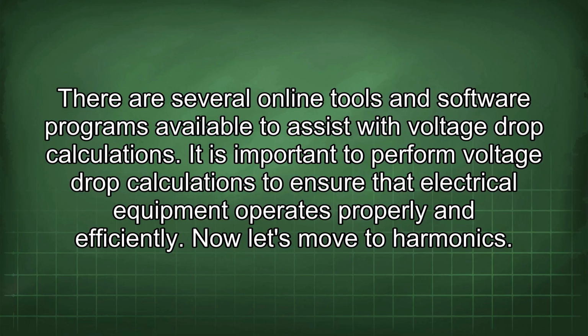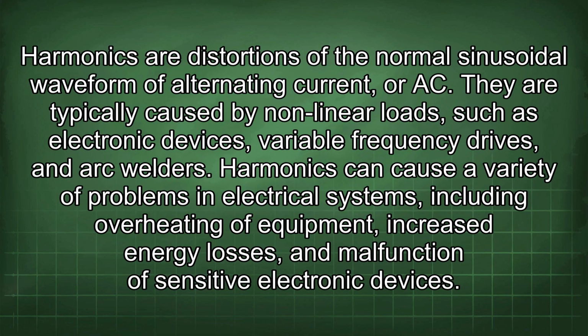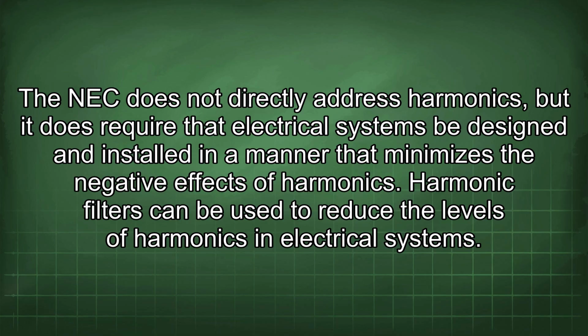Now let's move to harmonics. Harmonics are distortions of the normal sinusoidal waveform of alternating current, or AC. They are typically caused by nonlinear loads such as electronic devices, variable frequency drives, and arc welders. Harmonics can cause a variety of problems in electrical systems, including overheating of equipment, increased energy losses, and malfunction of sensitive electronic devices. The NEC does not directly address harmonics, but it does require that electrical systems be designed and installed in a manner that minimizes the negative effects of harmonics.